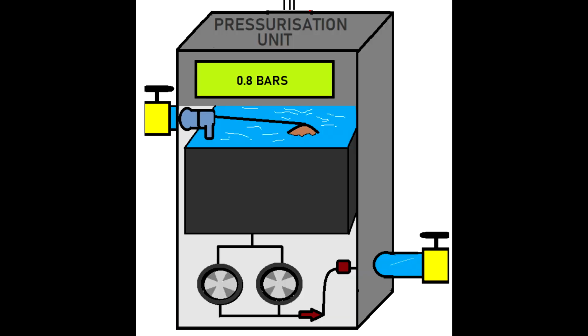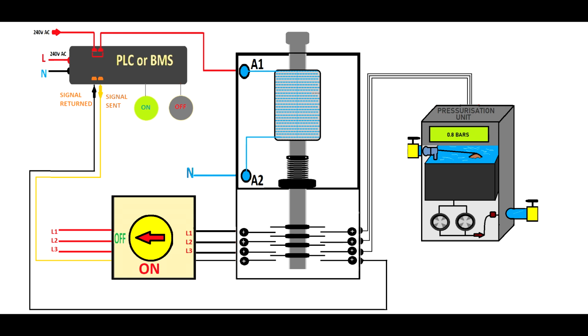Now, the same thing happens with the pressurization unit. The pressurization unit is normally directly connected to the power, but some people like to enable it via the programmable logic control. I will explain how the program should be written in this case. And they will enable the pressurization unit, which will follow its own protocol, because it has a printed circuit board inside. Now, this is your pressurization unit, it's ready to go.